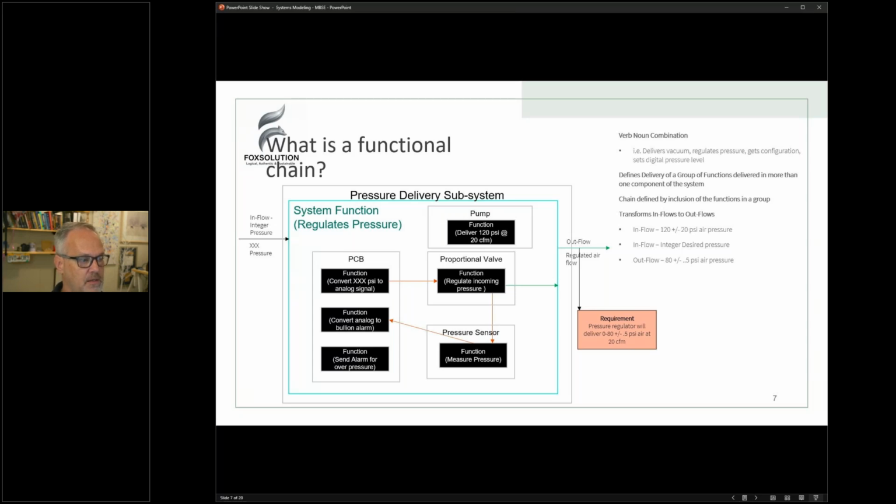One of the things we need to get into our head as we start writing requirements is: what's the formal difference between a design requirement, design level, and a system level requirement? When we say system level, a lot of times what I see in industry is that we write system requirements like, the system needs to be compliant with an ISO document. When you write requirements like that, you're characterizing not the function of the device, but compliance with an external standard.